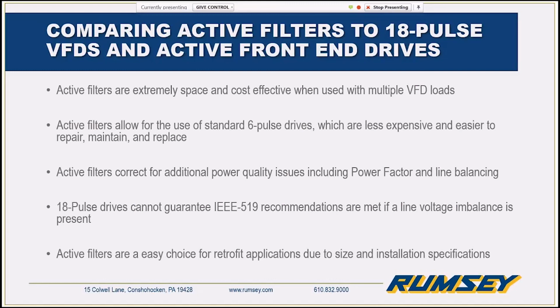18 pulse drives are a much older piece of technology, definitely tested, very large. That's usually one of the bigger issues with them. They take up a lot of real estate. Many drive manufacturers have moved away from them to move towards the active front-end drives, like Rockwell has with their 755 TL drive. You're going to want to look at active front-end drives or 18 pulse drives normally when you have a smaller quantity of loads because of the amount of space they take up. Again, with the active filter, looking at 3 or more VFDs totaling at least 150 horsepower.